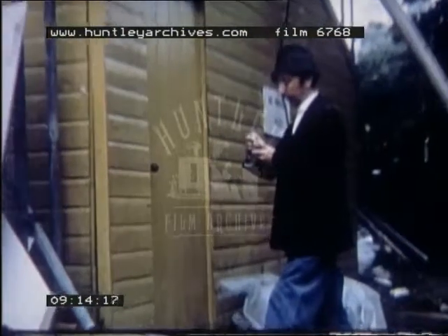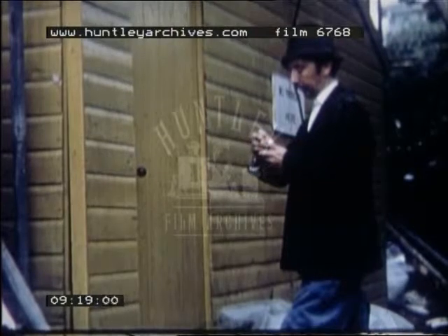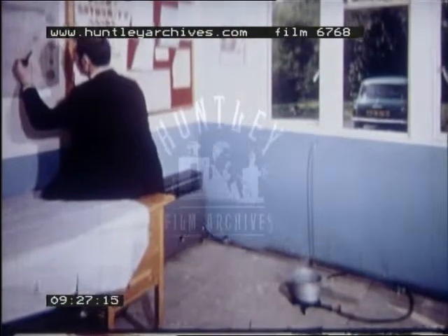This bloke doesn't think so. While he's rushing around from turning on the cylinder valve, gas is pouring out into the hut. Well, he learnt the hard way. All gas-fired heaters and boiling rings need air to work correctly, and so adequate ventilation is always required. Never close all the windows and never block up any ventilators.